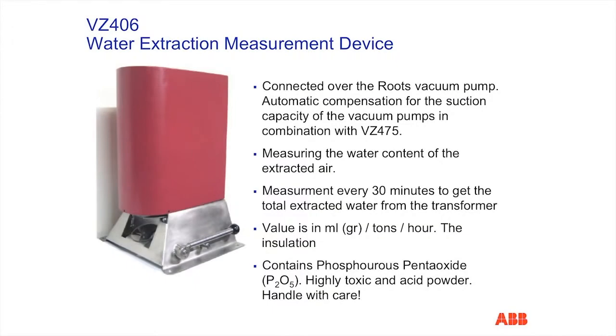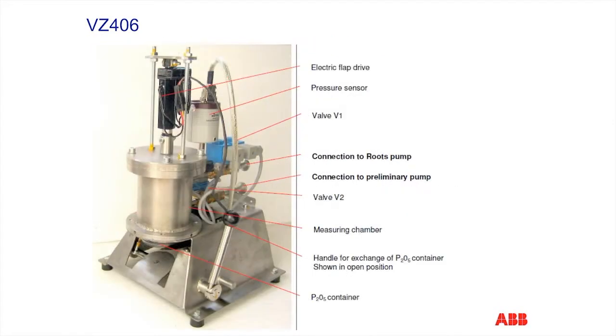Theory of the VZ406EL instrument. The purpose of this instrument is to provide the data necessary to calculate the amount of water that has been extracted from the transformer insulation during the entire low-frequency heating process. The instrument provides the suction capacity of the vacuum pumping system in cubic meters per hour and the concentration of water vapor in grams per cubic meter as a function of time.